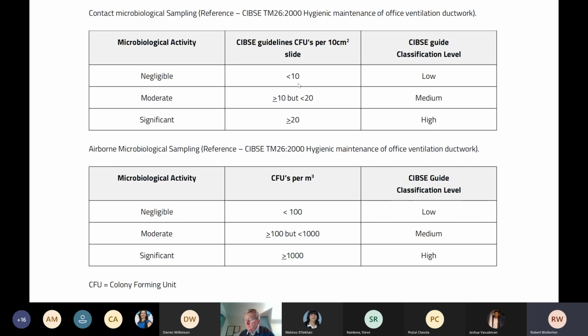Generally, they should only be used if there is a case within the building of someone actually coming down with an illness which could be from the ventilation system. And then TM26 advises in that instance, you should perhaps consider taking microbiological tests. We generally find the results on those can be very haphazard, if you like. They're not a good indication of cleanliness within the ductwork system.